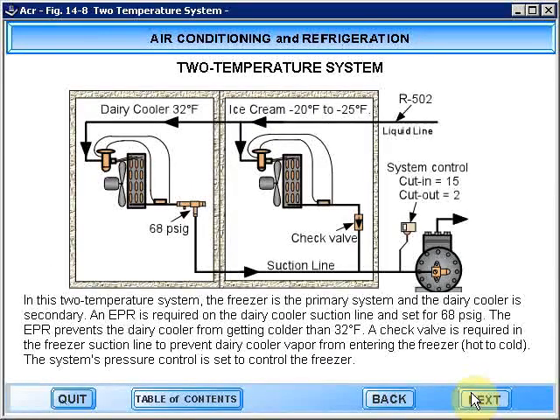In this two-temperature system, the freezer is the primary system and the dairy cooler is secondary. An EPR is required on the dairy cooler suction line and is set for 68 pounds gauge. The EPR prevents the dairy cooler from getting colder than 32 degrees. A check valve is required in the freezer suction line to prevent the dairy cooler vapor from entering the freezer, in other words, hot to cold. The system's pressure control is set to control the freezer.